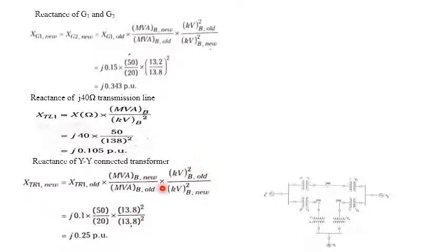So what is the value we got? It means the transformer side. Okay, 13.8 divided by 13.8. Look at this, this is referred to the transformer. There is no change in the value of the transformer. 13.8 divided by 13.8, you will get 0.25. Or else, if you get confused, you go for the ST rating of the transformer side. So that is 138 by 138, it cancels, and you will get 0.25.